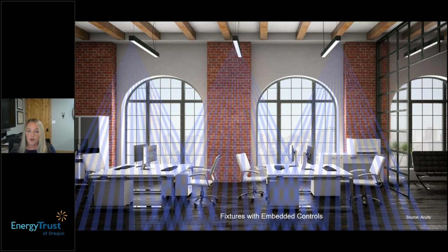If I were in the room previously and walked in to get something off that desk, all three light fixtures might turn on. That's a possibility. But with LLLC and embedded controls, you can see the granularity and coverage pattern - if I walk in and grab something off that desk, probably just the first fixture turns on. Or I could have it in vacancy mode where it doesn't turn on at all. It's really that granularity of each fixture having an embedded sensor.